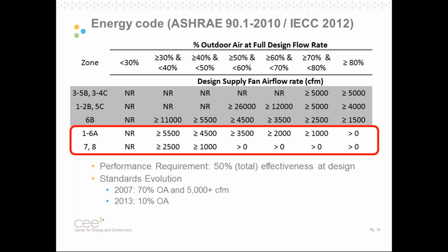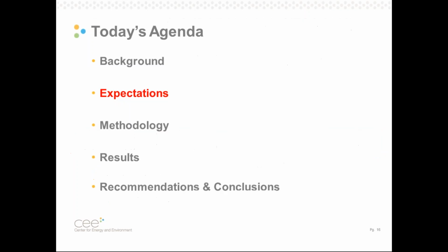This is an upgrade in requirements from previous ASHRAE standards. I think from 2007, we only had to implement energy recovery at 70% OA and 5,000 CFM. But if we look at the trend, the 2013 90.1 standard increases the requirements for energy recovery down to systems with 10% OA. So from this, we conclude that they're getting fairly aggressive about energy recovery requirements in code, and that's because, frankly, from a theoretical perspective, they save a lot of energy, and from a practical perspective, they do so very cost effectively, often even lowering first costs.